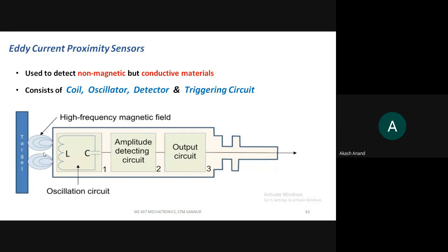The working principle is that a circular current will be induced in a conductor when it is placed in a changing magnetic field. Imagine the high-frequency magnetic field produced here as a changing magnetic field. If a non-magnetic type conductor is placed here, a circular current called eddy current will be induced in that conductor.